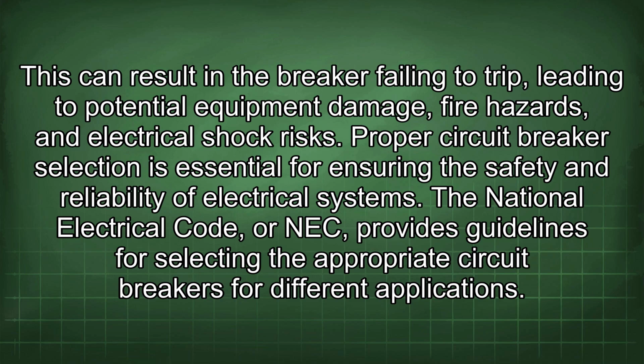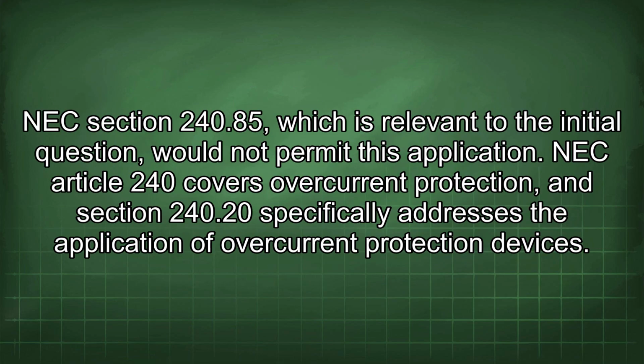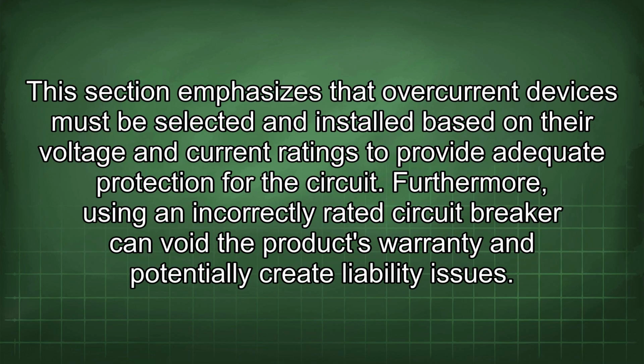The National Electrical Code, or NEC, provides guidelines for selecting the appropriate circuit breakers for different applications. NEC Section 240.85, which is relevant to the initial question, would not permit this application. NEC Article 240 covers overcurrent protection, and Section 240.20 specifically addresses the application of overcurrent protection devices. This section emphasizes that overcurrent devices must be selected and installed based on their voltage and current ratings to provide adequate protection for the circuit.